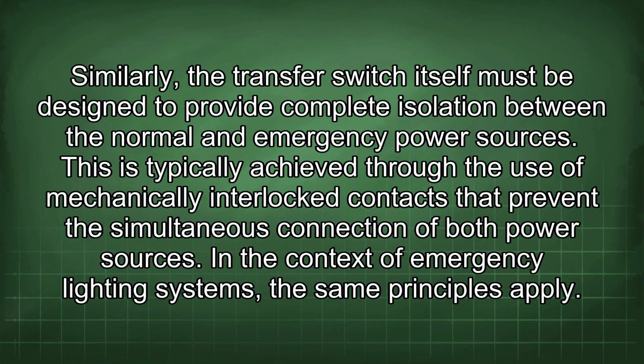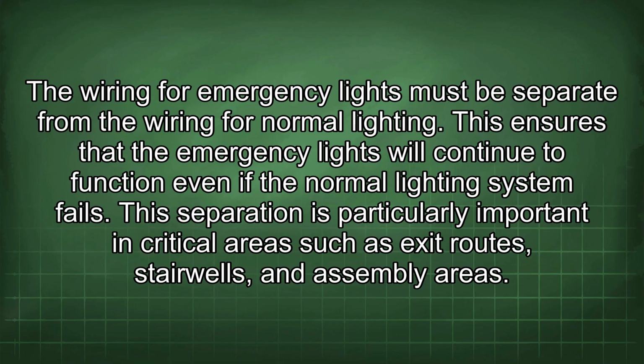In the context of emergency lighting systems, the same principles apply. The wiring for emergency lights must be separate from the wiring for normal lighting. This ensures that the emergency lights will continue to function even if the normal lighting system fails. This separation is particularly important in critical areas such as exit routes, stairwells, and assembly areas.